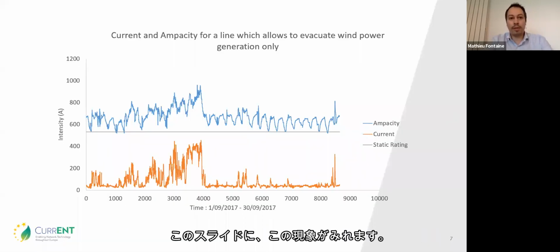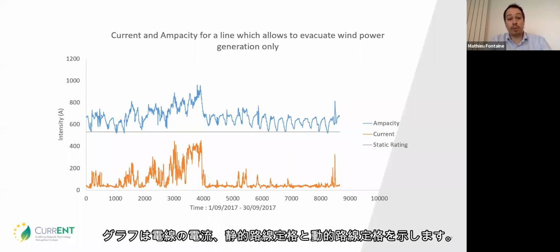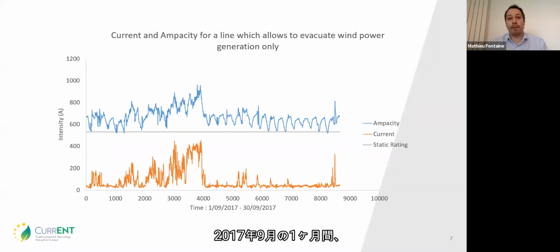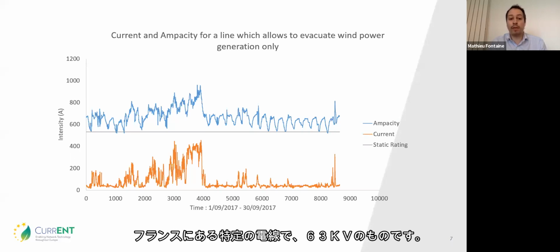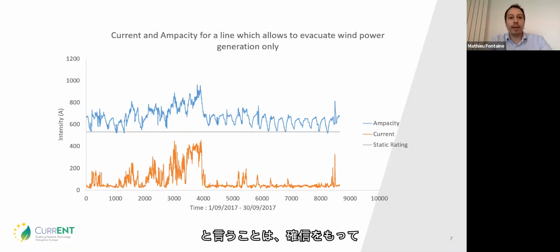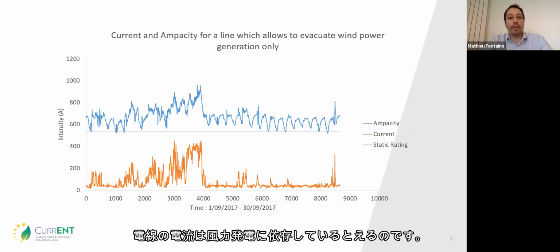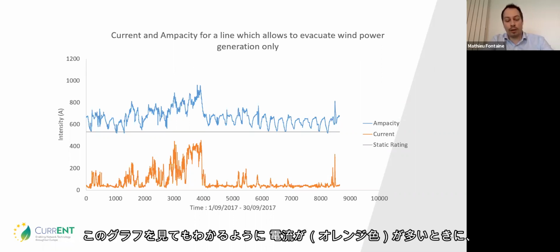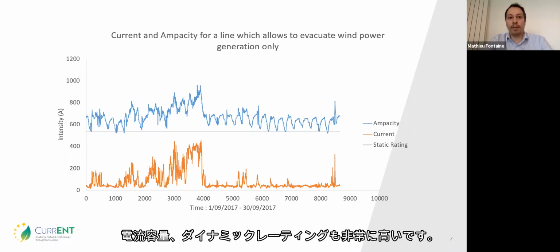On this slide, the graph illustrates the current, the static rating, and the dynamic line rating for September 2017 for a specific 63 kV line in France. This line only evacuates wind power generation, so we're sure the line current depends solely on wind power generation. As we can see, when the current in orange is high, the dynamic line rating is also very high.